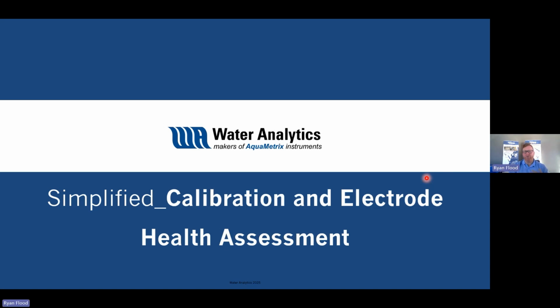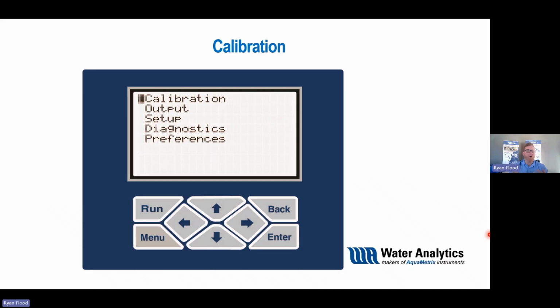Calibration and electrode health. This is where a lot of times it's really important to be thinking about how your sensor is working, and you want to get it up and running. So I just want to walk through a quick little demo here on one of our 2250 series controllers. So you'll start off your process, it's wired up, it's working, and you don't think the sensor is reading well. So you want to perform calibration.